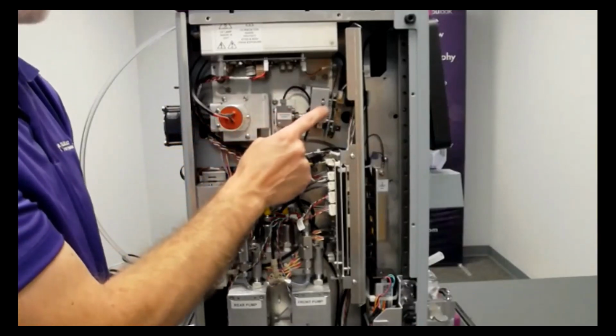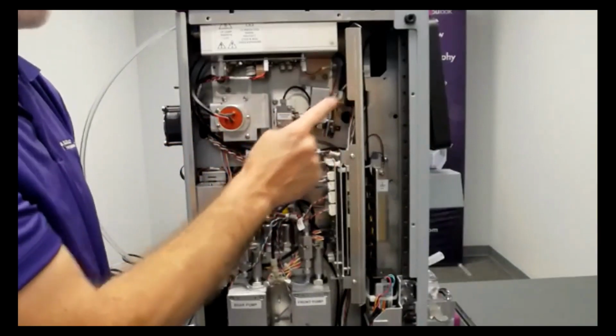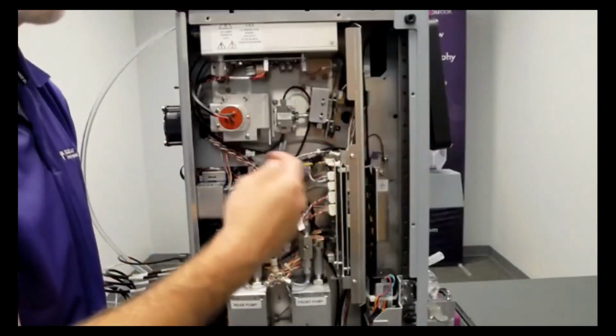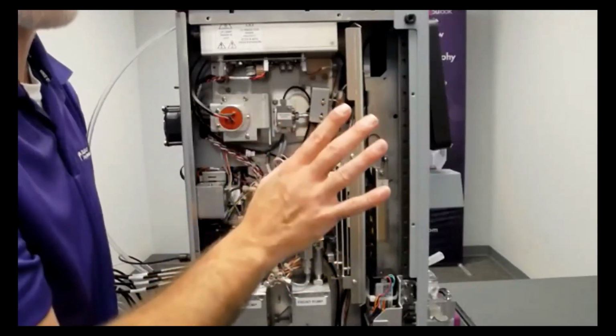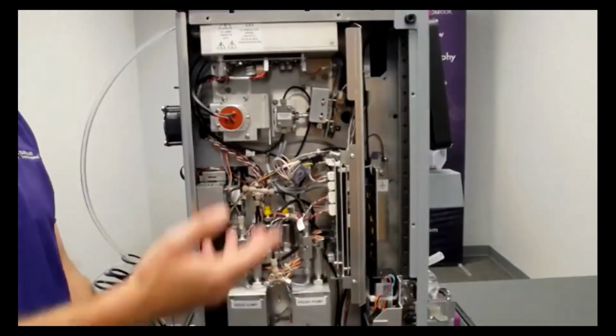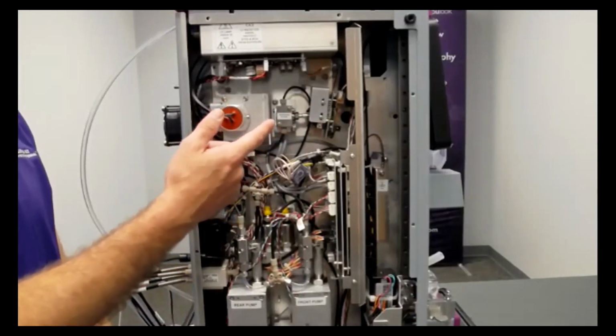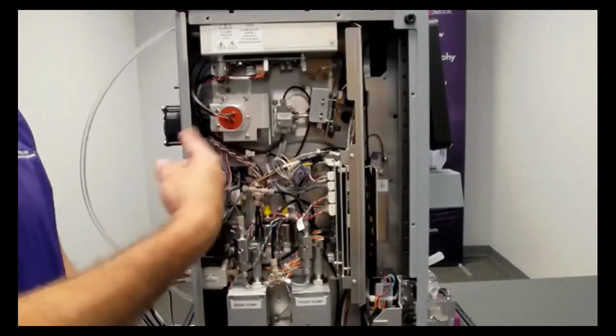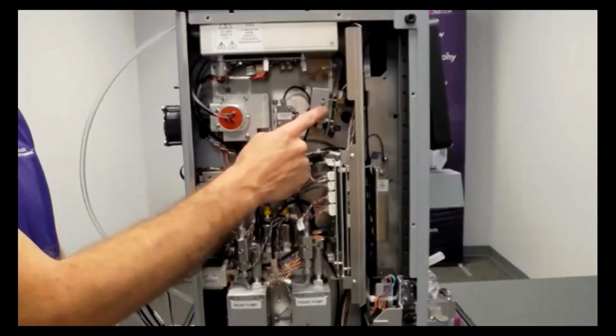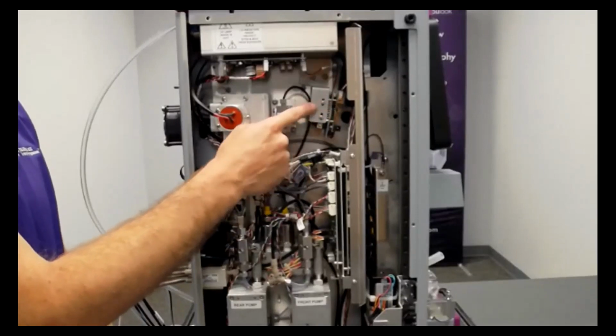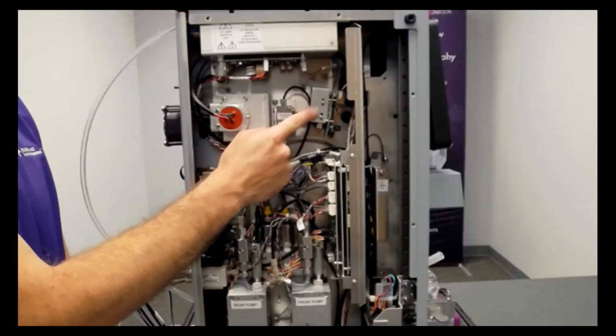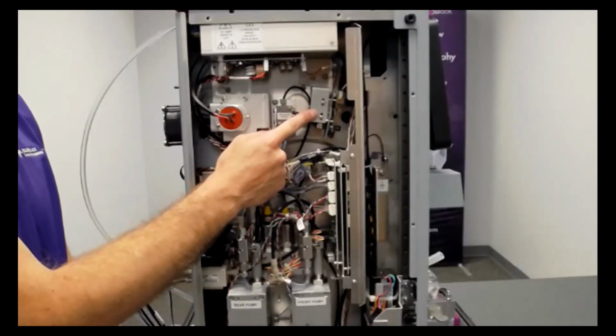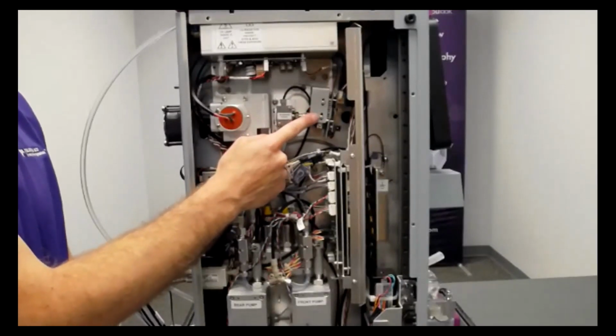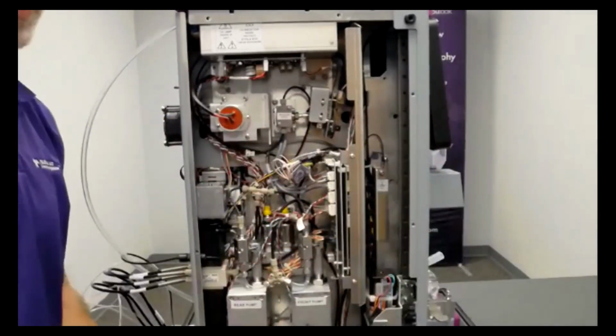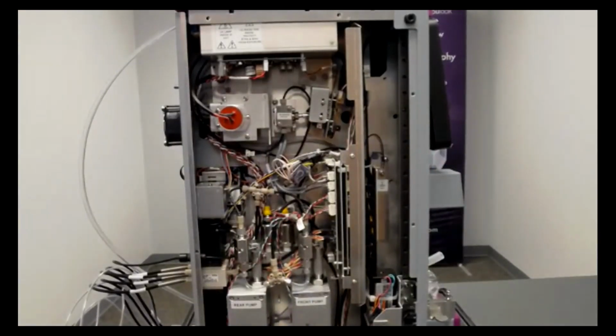And this guy, the detector, is telling the unit it's absorbing at 254. Oh, we've got an absorbance at 280. Or whatever you have it set for. 254 and 280 are kind of the defaults that we look for, but there are all wavelengths that you can turn on where it's doing the entirety of the spectrum that it can handle. So we have a UV or we have a UV vis detector. The UV does 200 to 400, I believe, and the UV vis does 200 to 800. So it's a much wider range of spectrum for the detection there.